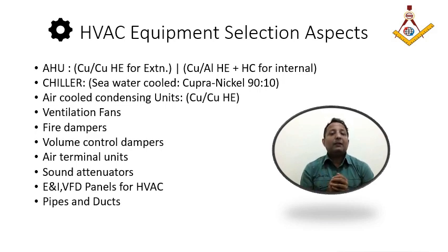When it is inside, the coil material has to be copper aluminum. If it is outside, it has to be copper with a Heresite coating, which protects the cooling coil and fins from corrosion, since copper aluminum fins are still susceptible to corrosion due to the saline environment outside.